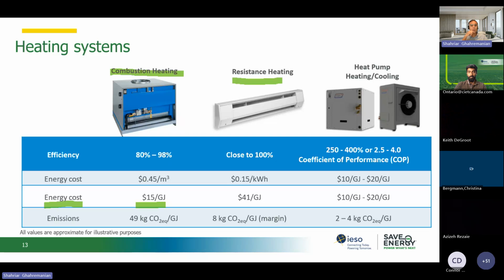If we just install a resistance heating system like this baseboard that you see here, the energy cost becomes $41 per gigajoule. So this is super expensive. Maybe the best wording is that it's not a good idea. It doesn't make sense. $15 versus $41 is almost three times more expensive. So forget this system. But what about the heat pump for heating and cooling?